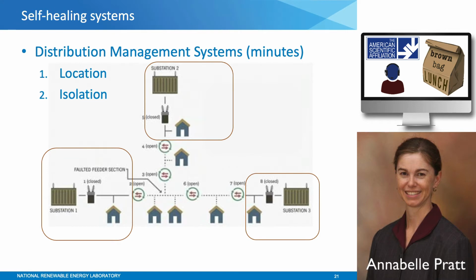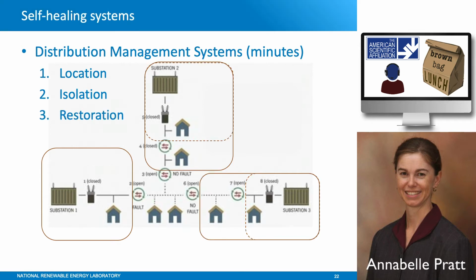This is where new technology comes into play: distribution management systems. These are software systems that utilities are starting to deploy. I'd say maybe 30% of residential customers in the United States are served by a utility that has a distribution management system. It's just starting to be used, taking real-time feedback from the field to locate the fault, running algorithms to locate it, make sure it's isolated, and then restore service.